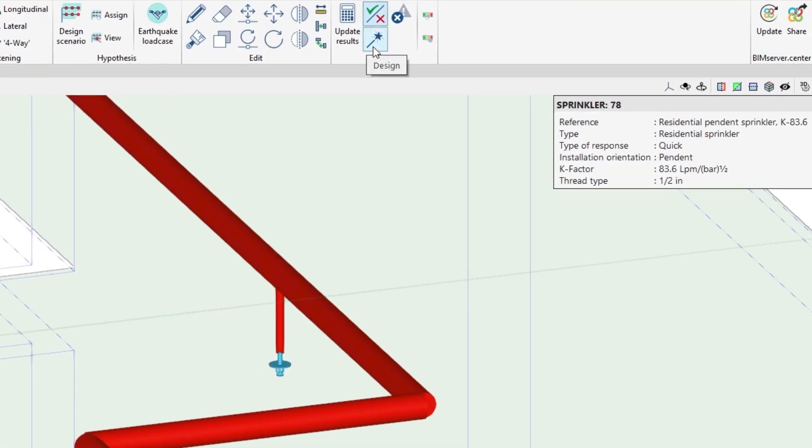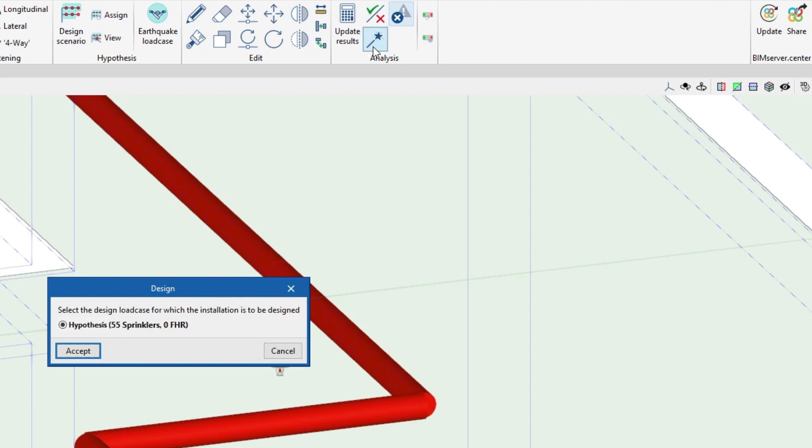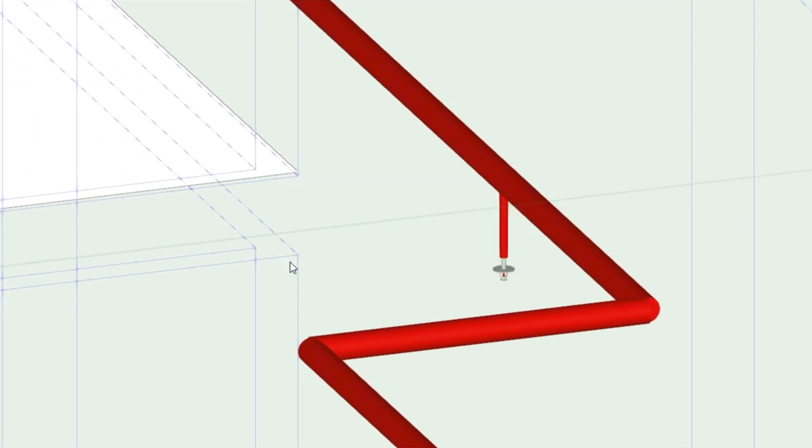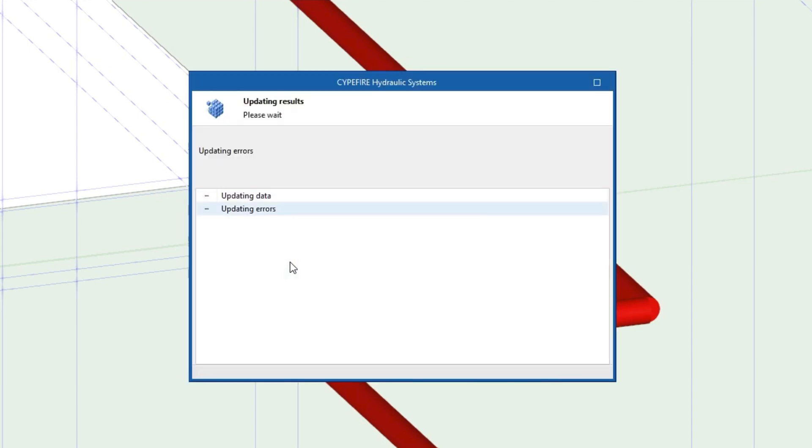The program can also carry out the automatic design of the pipes, selecting their diameter according to the number of sprinklers they feed and complying with the indicated checks through several iterations.